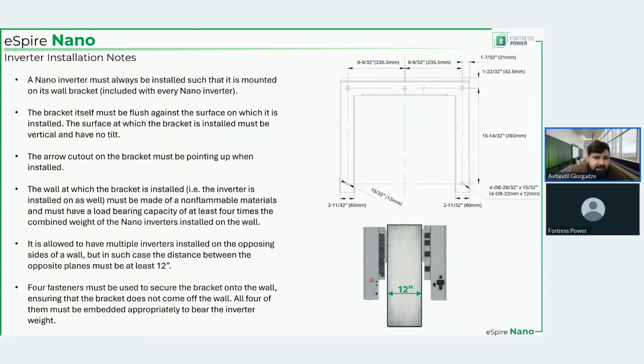The bracket must be flush against the surface on which it is mounted, so no gaps anywhere. It is very important that the bracket has the arrow cutout pointing up, because you hang this inverter on top of this bracket. If the arrow is pointing down, there's nothing to hang the inverter onto.